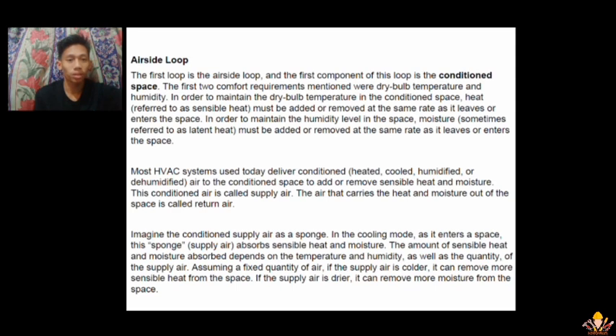Most HVAC systems used today deliver conditioned (heated, cooled, humidified, or dehumidified) air to the conditioned space to add or remove sensible heat and moisture. An example is to imagine the conditioned supply air as a sponge. In the cooling mode, as it enters a space, the sponge, or supply air, absorbs sensible heat and moisture. The amount of sensible heat and moisture absorbed depends on the temperature and humidity as well as the quantity of the supply air.